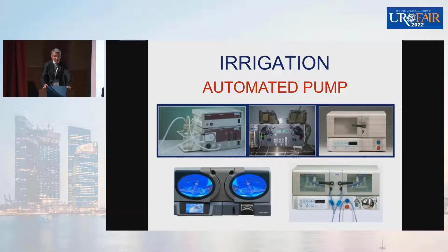Automatic pump. Remember that these pumps are supposed to be a great tool to regulate the pressure. Be careful of the placement of the pump compared to the patient. If you place the pump 20 centimeters above the patient and you set 50 centimeters on the pump, you will have to add the 20. So it's not 50, it's 70.